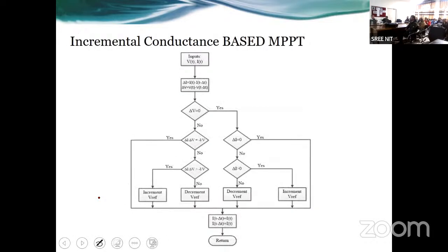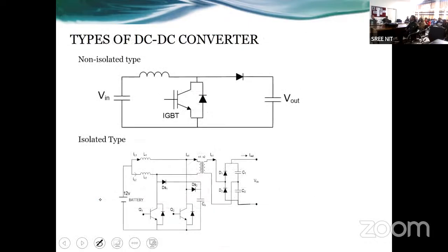This is also the incremental conductance based MPPT method. Now, types of DC-DC converter: normally we have a boost converter, because the solar side DC voltage is low, and on the grid side or DC output side it needs to be high. You can have an isolated type system, where a high frequency transformer is there, so grid side disturbance is totally isolated from the solar panel, or vice versa.